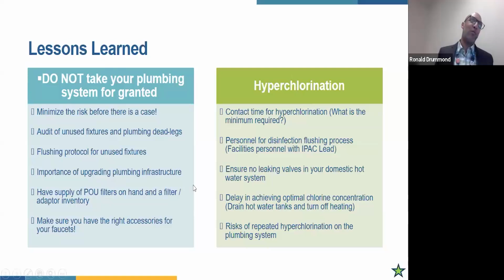Hyperchlorination—contact time is really, really important. However, as a facilities guy, I've got to say hyperchlorination is terrible for the condition of my copper pipes. The longer chlorine stays in the system, the more biofilm gets removed, but also some of the wall of the pipes come apart. So you should expect during hyperchlorination that you'll have some areas with leaks. For that reason, I suggest disinfection be facilities led, and call in additional contractors if required, so you can deal with leaks as you go and not lead to other issues like mold growth or staining of walls.